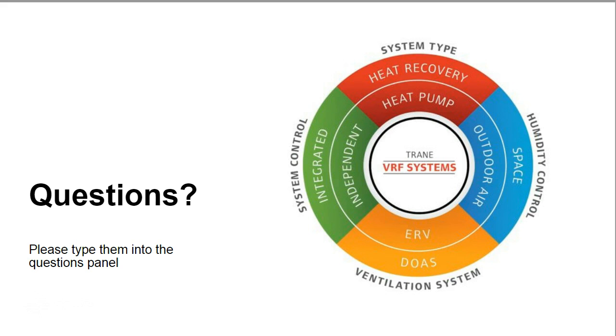I highly recommend also using isolation refrigerant ball valves, especially for when you have to take a unit down for some unseen error, or for adding additional terminal zone units to your system later on.